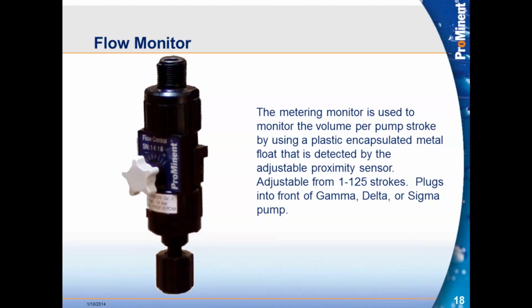If it doesn't see that signal come back, it starts counting the number of consecutive strokes without that feedback, and it will put the pump into a fault after that predetermined number. You can see you can adjust that up to 125 consecutive strokes without feedback before the pump goes into a fault. So if we're pumping and we missed 80 strokes, and then all of a sudden we get one with feedback, we have to go 125 again before we put the pump into a fault.